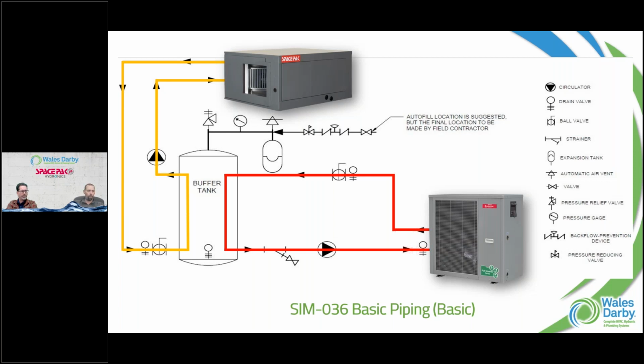Thinking about what we've been doing hydronically for heating, and switching that over to having one appliance do both heating and cooling. There are other piping layouts too, maybe dual tanks with isolation — it's amazing to have a hot tank and a cold tank. That 120 degrees is really where we want to understand the envelope of the building. If it doesn't require more BTUs, why keep beating it up with 180 or higher degree water? It's a waste. So we get more efficiency, and even though it's electric — right now we're talking 100% straight electric, but now we're talking refrigerant based, inverter stuff with DC processing, really boosting our BTUs per kilowatt of energy. That's where you'll see big outputs in energy dollars.